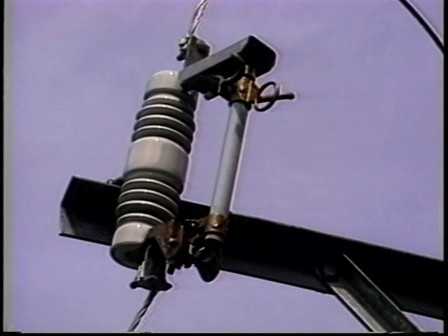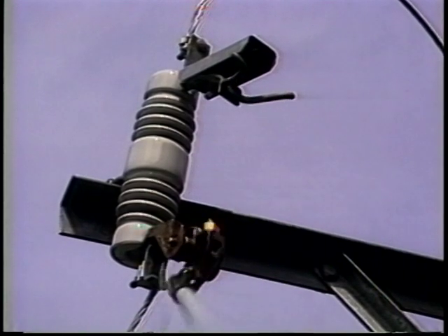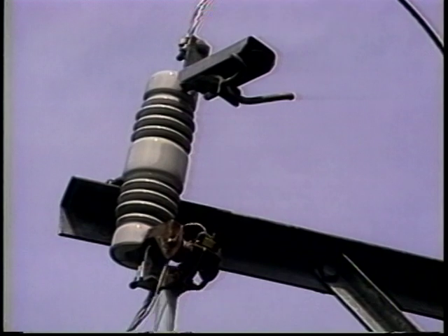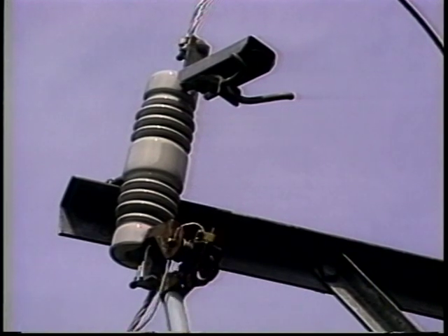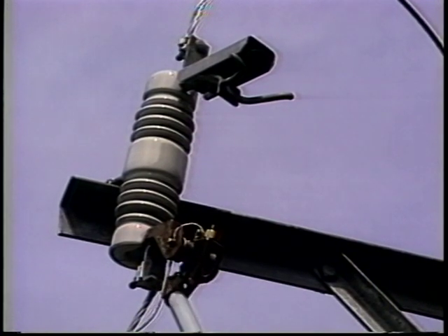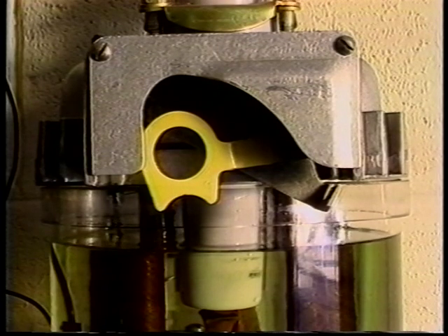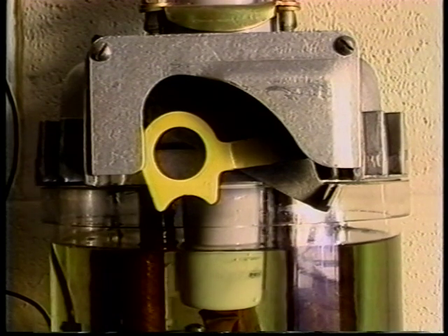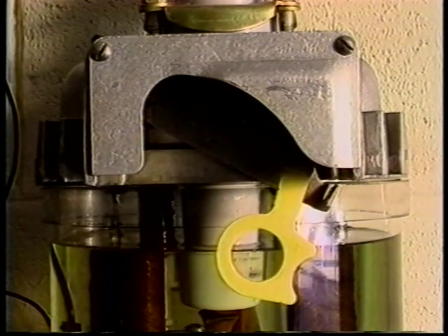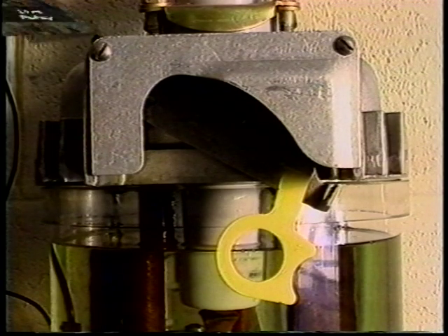If the fault is permanent, the recloser goes into time-delayed tripping operation and permits sectionalizing devices, such as fuse beyond the recloser, to open and isolate the fault. If a permanent fault should occur between the recloser and the next sectionalizing device out on the line, the recloser then goes to lockout and isolates the fault.